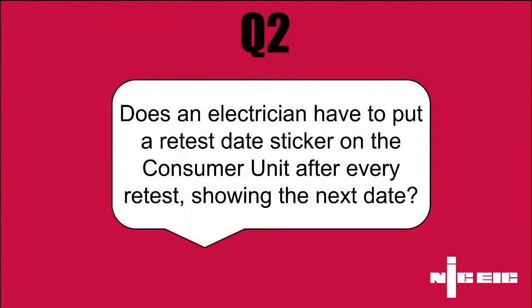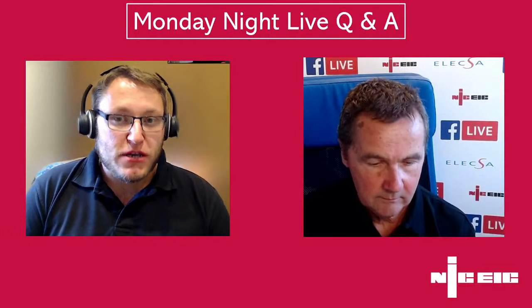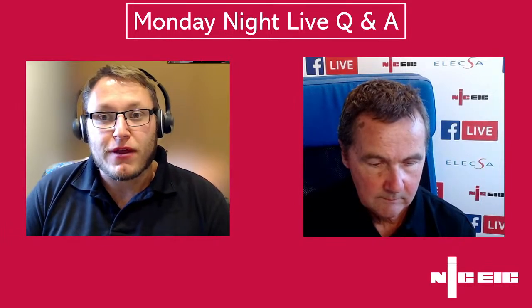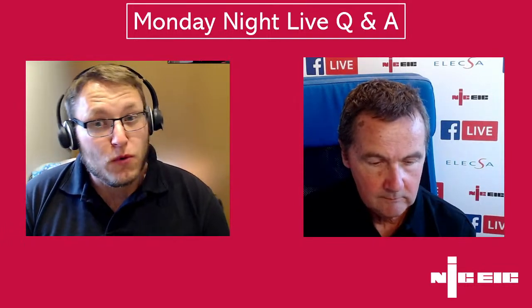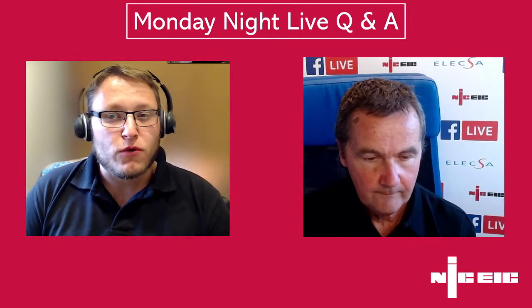Another one that's been hanging around for a while is: does an electrician have to put a retest date sticker on the consumer unit after every retest showing the next date? So what are your thoughts around that, Craig? So the answer for this is yes, because the requirements for the labelling fall under section 514, specifically 514.12.1.